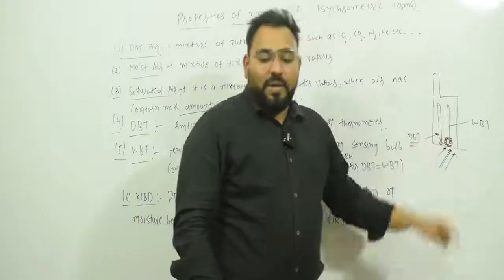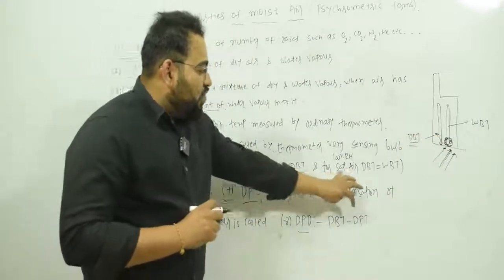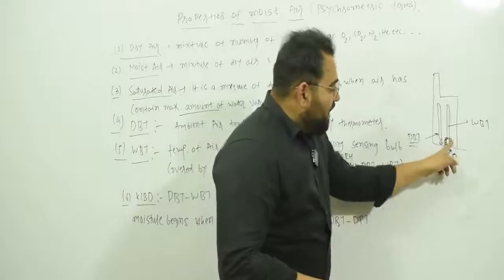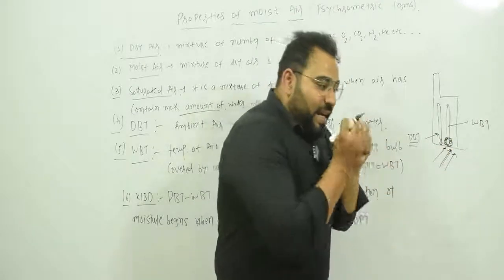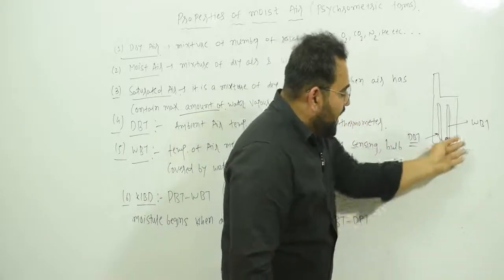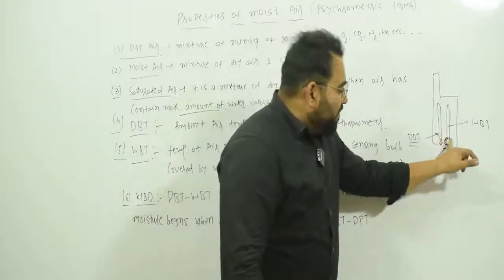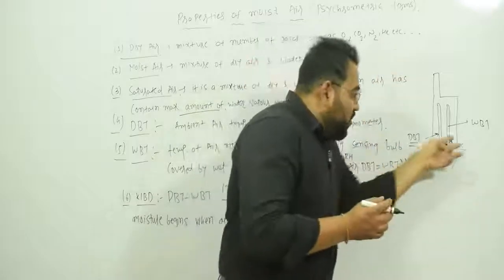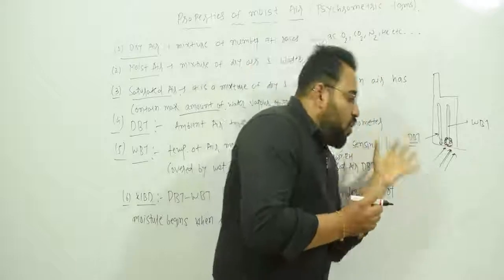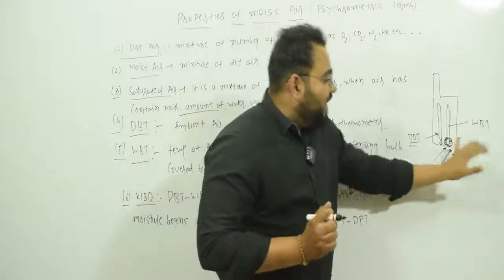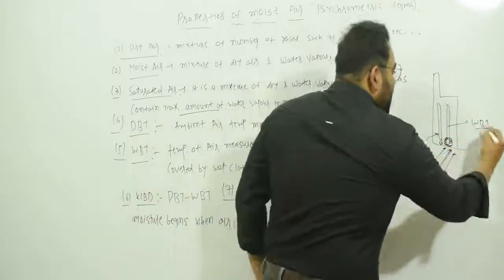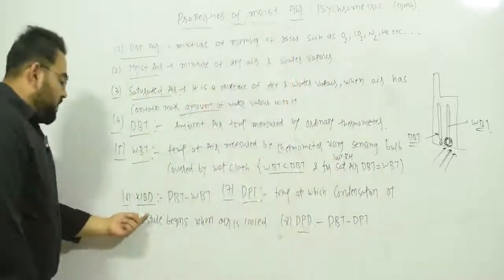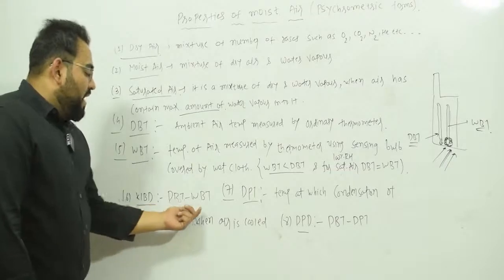Always remember: wet bulb temperature is less than dry bulb temperature because evaporation causes cooling. However, for saturated air — that is, at 100 percent relative humidity — dry bulb temperature equals wet bulb temperature. This is because when saturated air passes over the wet cloth, evaporation does not occur, as the air is already holding its maximum amount of water vapor and no more can be added.